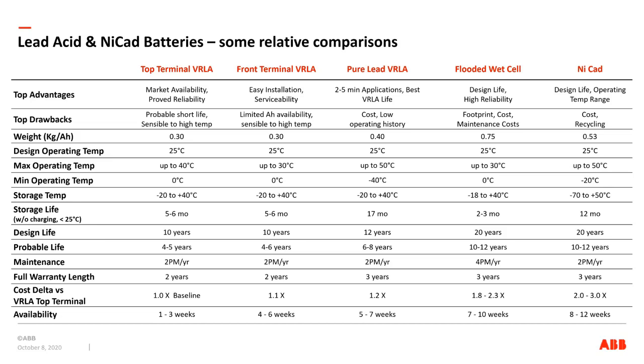And then, looking at what we talked about, the flooded wet cell and the NiCad, there are a lot of similarities between the two. Interesting, and that actually goes across the board, in the UPS world for battery energy storage, we talk about battery design life. And funny enough, nobody expects the battery to live that long. VRLA is typically a 10-year design life, and most customers swap batteries every 4 years, some even every 3 years. Sometimes you get a little bit more out of them, but they typically live about half the design life. And that's true for most of them.